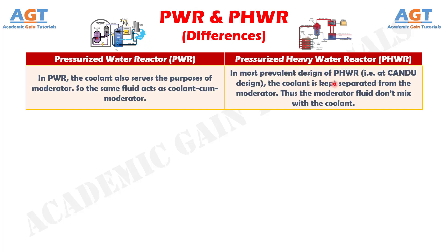Difference number 1. In a pressurized water reactor, the coolant also serves the purpose of moderator — the same fluid acts as coolant-cum-moderator. Whereas, in the most prevalent design of pressurized heavy water reactor, the coolant is kept separated from the moderator. Thus the moderator fluid does not mix with the coolant.